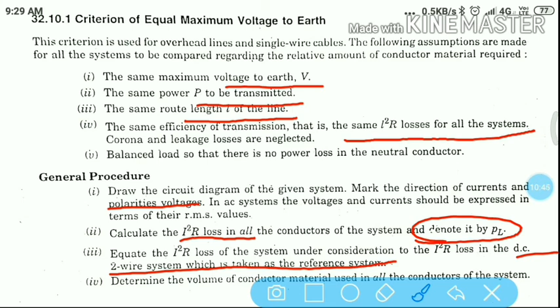A general procedure for the criterion of equal maximum voltage. Number 1: draw the circuit diagram of the given system. Mark the direction of current and polarity of voltage. In an AC system, voltage and current should be expressed in terms of RMS values. Calculate the I squared R loss in all the conductors of the system, denoted by PL. Equate the I squared R loss of the system under consideration to the I squared R loss in the DC two-wire system, which is taken as the reference system. Determine the volume of conductor material used in all the conductors of the system. And last, determine the ratio of the volume of conductor found in step 4 to the volume of conductor used in the DC two-wire system with one wire earthed.